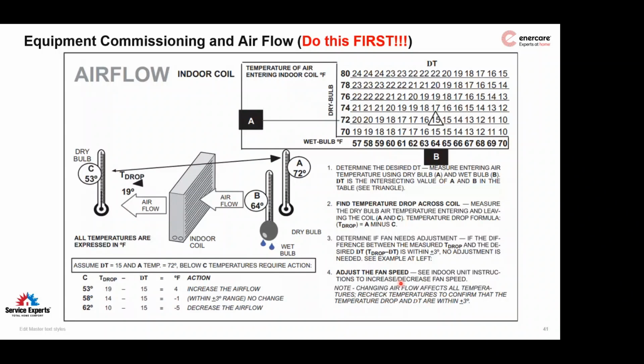This is Lennox's setup in their manual. Wet bulb and dry bulb give you an expected delta T across the coil. So if you were to use this example on their chart, with a 64-degree wet bulb temperature and a 72-degree dry bulb temperature, Lennox expects across your coil you'd have 15 degrees, plus or minus 3 degrees. If you have more than that, like they show right here in their first example at 53 degrees, which is 19 degrees, there's a really good chance that you've got inadequate airflow and the airflow needs to be increased.